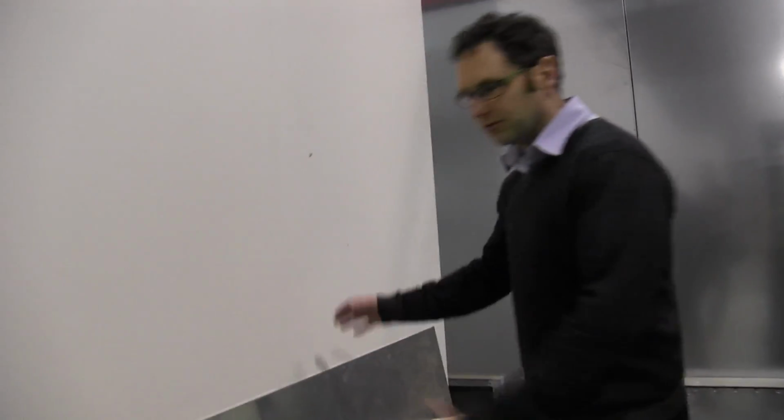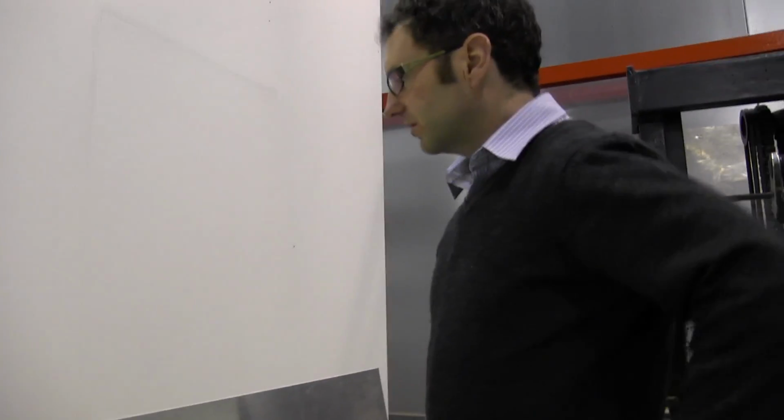There's a couple of different tests. If it's just a small product, we'll put them in the middle. But another part of the testing is we test just the cables. So imagine this on the floor, obviously. The product's up there, and you lay the cables all the way out to the power supply there. Because these are only for low frequencies. What sort of frequencies are we talking about? A meg up to a couple of hundred, 400 megs. And at those frequencies, it's the cables that the RF is going to couple onto, not the actual product.